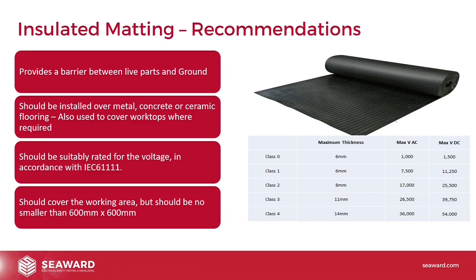So if the tester can output 6 kV, that's the protection that we are looking for. So rather than go for a class 0, we're going to go for a class 1. You should cover the whole working area, but the working area should be no smaller than 600 millimeters by 600 millimeters, about 60 centimeters by 60 centimeters. This matting usually comes in rolls, as in that picture there, about 1 meter by, say, 10 meters. So usually the working areas end up being around 1 meter by 2 meters, giving the operator enough space to move around.